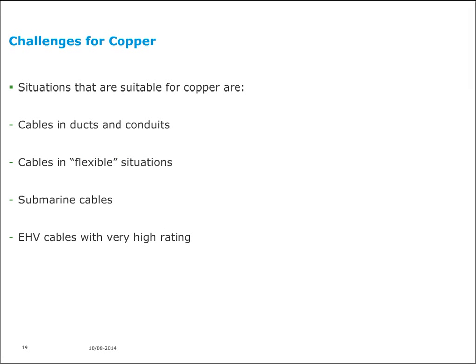Well, situations that are suitable for copper are cables in ducts and conduits, because there the radial size is relevant. The bigger the cable, the less problems you have with pulling in. Cables in all kinds of flexible situations, because the bending becomes more difficult with increased radial dimensions. In submarine cables, because we learned that in submarine cables, the heavier cable has an advantage. It's more stable on the bottom of the sea, and it can enter the sea trenches more easily when it has more weight. And finally, for extra high voltage cables, it's very high rating.